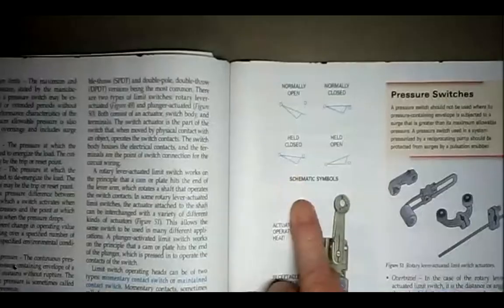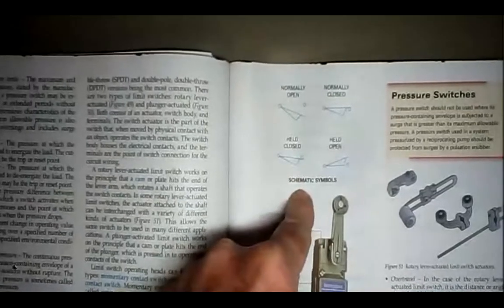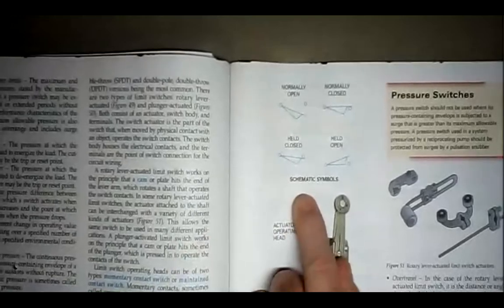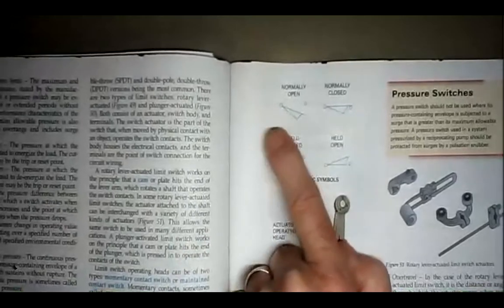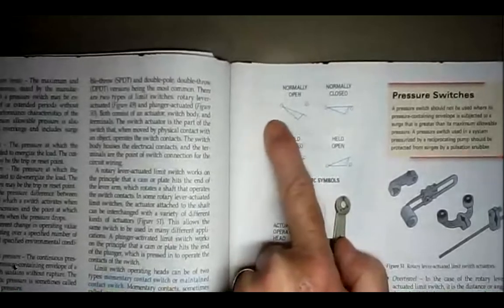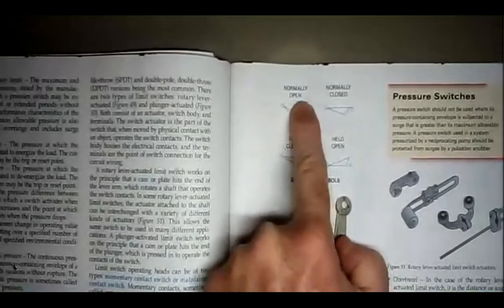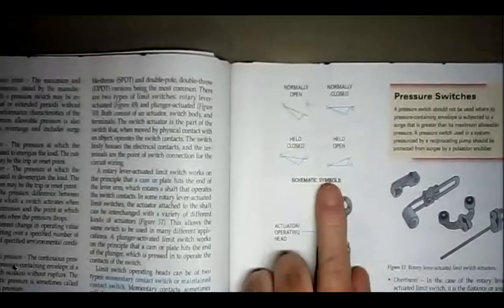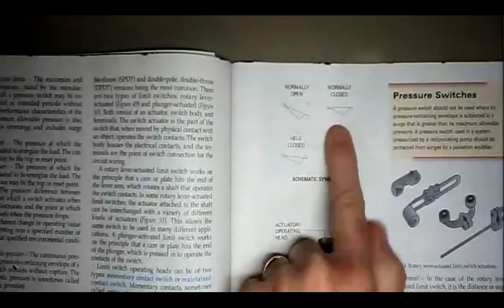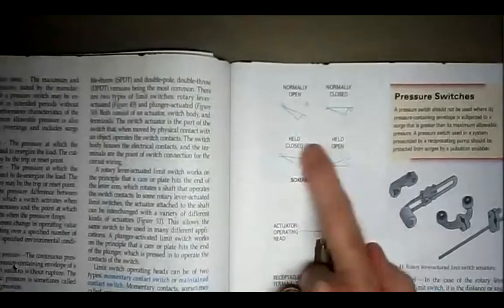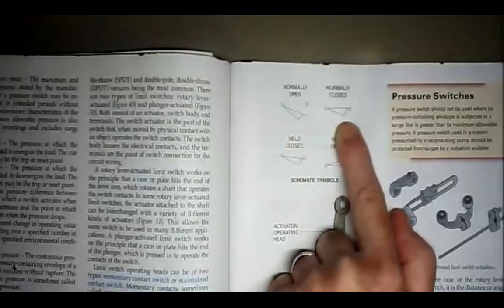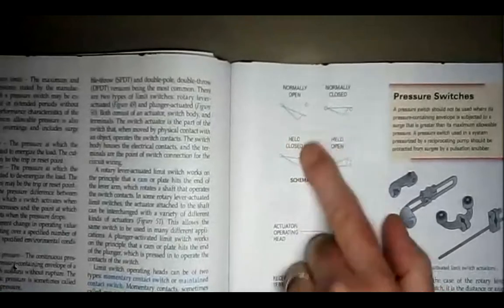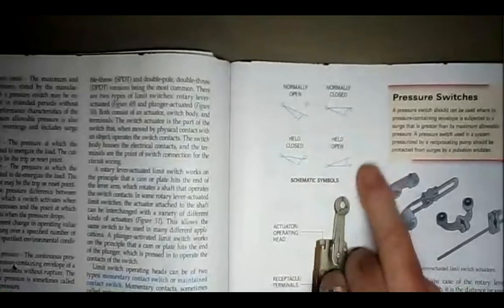This one's not highlighted, but it's a limit switch, meaning that something's going to come down a conveyor or it's going to move, and when it hits this switch, it's going to close that switch. Okay. And I don't like their drawing here. There you go. That's what I would have. Oh, this is held closed. Okay. Here's normally open, held closed, normally closed, held open. That's the limit switches.